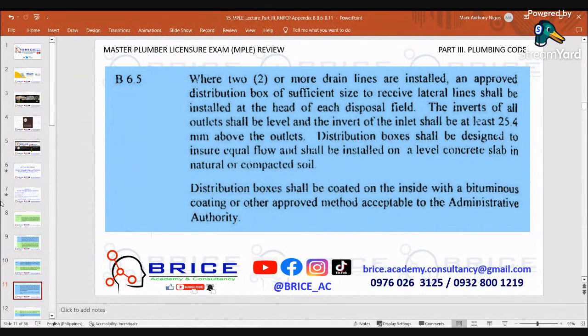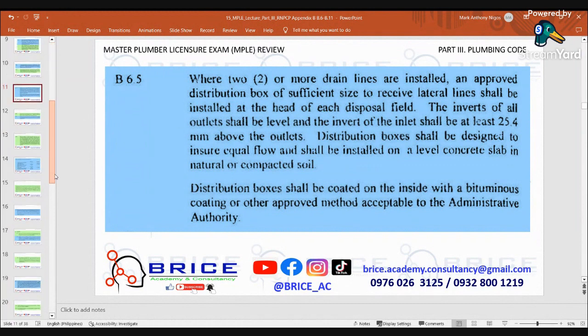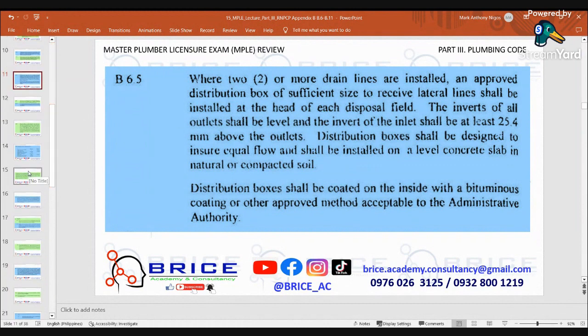Where two or more drain lines are installed, an approved distribution box of sufficient size to receive lateral lines shall be installed at the head of each disposal field. Inverts of all outlets shall be leveled and the invert of the inlet shall be at least 25.4 mm above the outlets. Distribution boxes shall be designed to ensure equal flow and shall be installed on a level concrete slab in natural or compacted soil. Distribution boxes shall be coated on the inside with a bituminous coating or other approved method acceptable to the administrative authority.